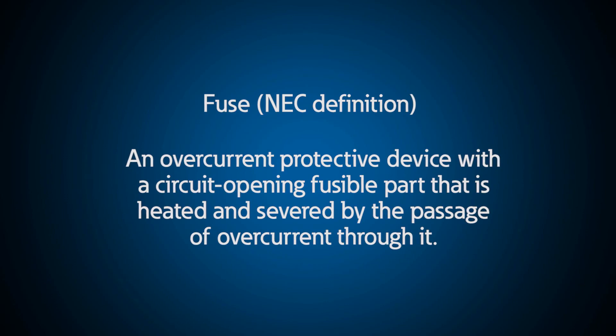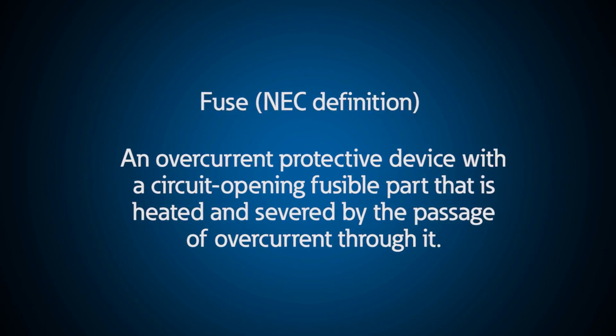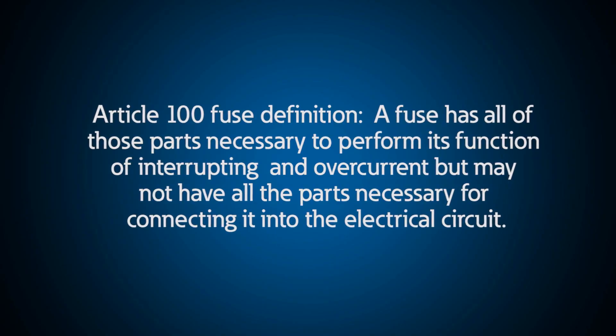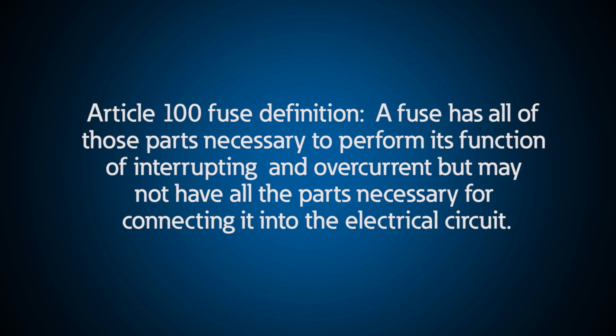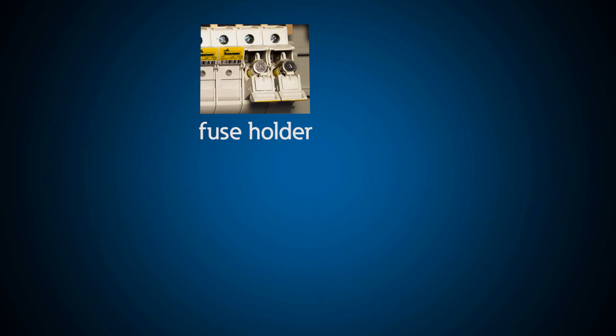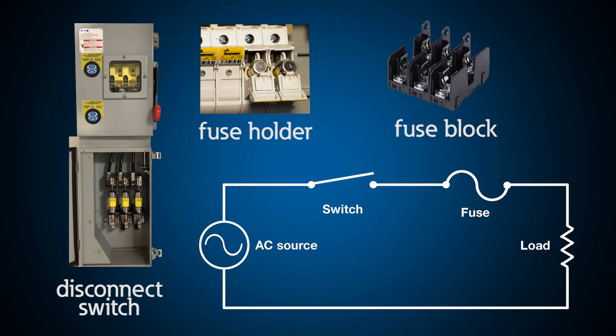The National Electrical Code defines a fuse as an overcurrent protective device with a circuit-opening fusible part that is heated and severed by the passage of overcurrent through it. The NEC notes that the fuse has all parts necessary to interrupt an overcurrent, but may not have all parts necessary to connect it into the circuit — requiring a fuse holder or fuse block and a switch to enable replacement.